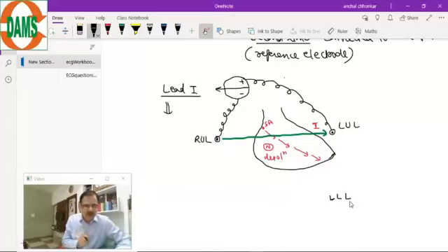Because we know the net direction of the normal depolarization is towards the left side, for the majority of the lead system the exploring electrode will be towards the left side, so that we'll see positive deflections. So here, from the left upper limb, the wire will go to the positive pole. From the right upper limb, the wire will be connected to the negative pole, and this will be the vector line of lead 1. The vector line of lead 1 is the green line.